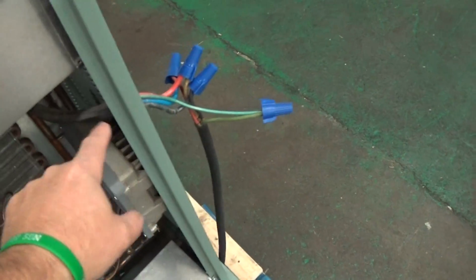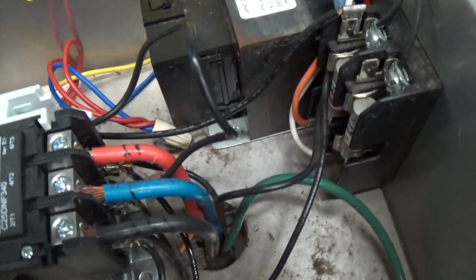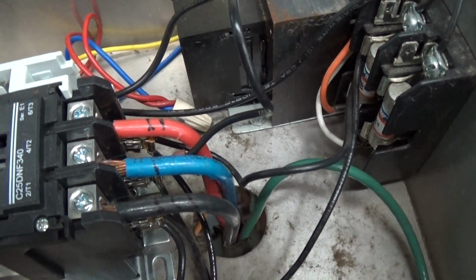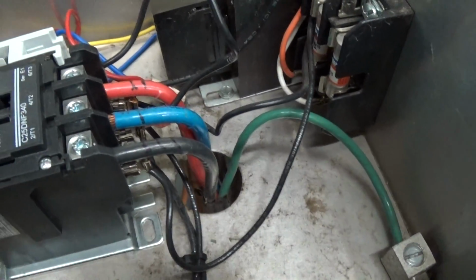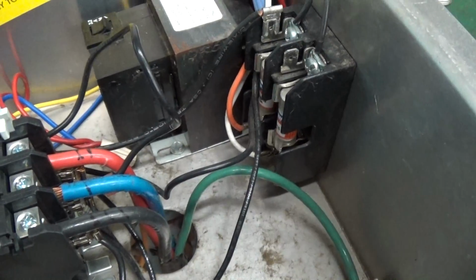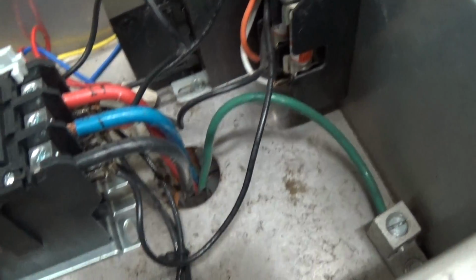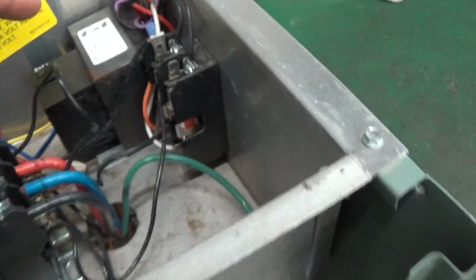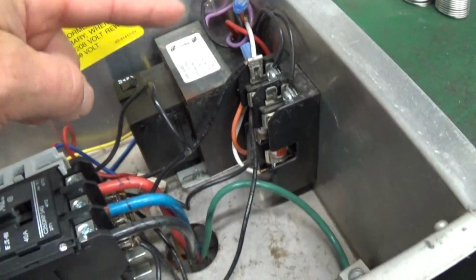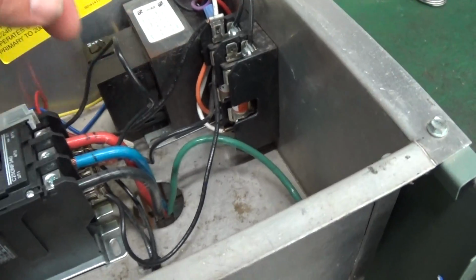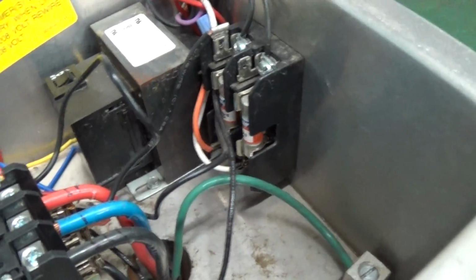So we have just our test cable coming in here for the incoming power. That comes into our main contactor here, where you see black, blue, and red, and then obviously a ground too. This customer says their three-phase power has a wild leg. You don't see that too often anymore. The main thing is you see this controller transformer here, and you've got to look closely.